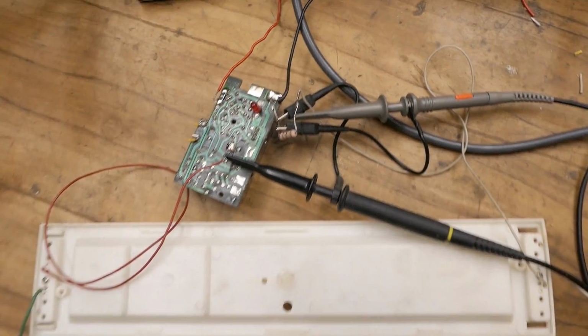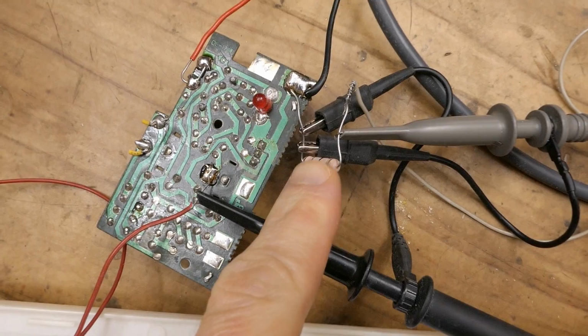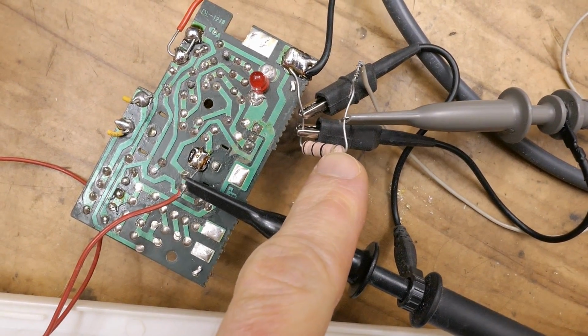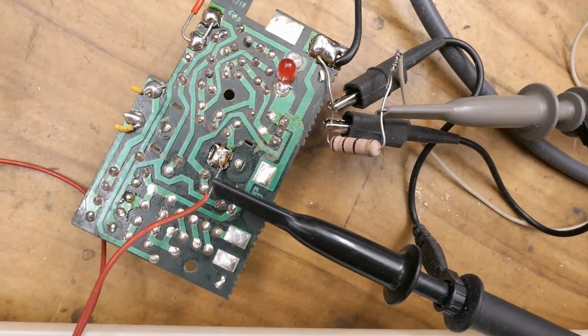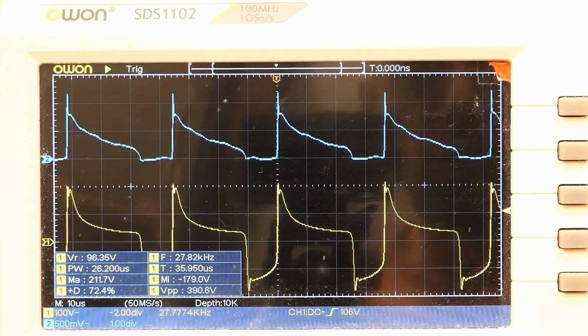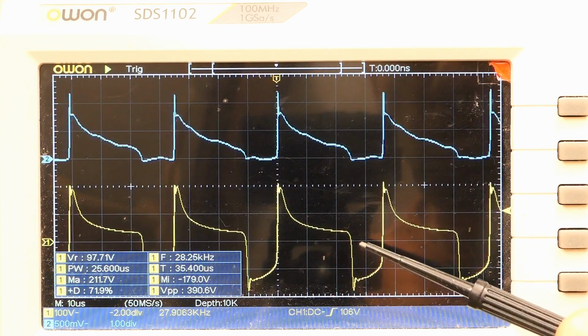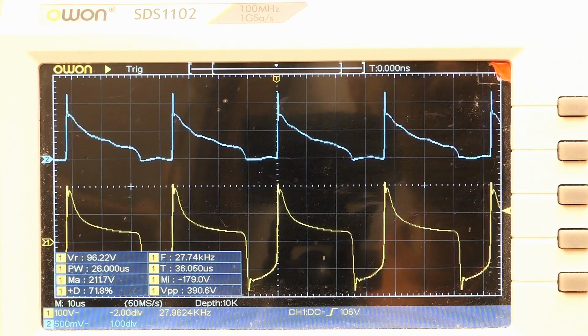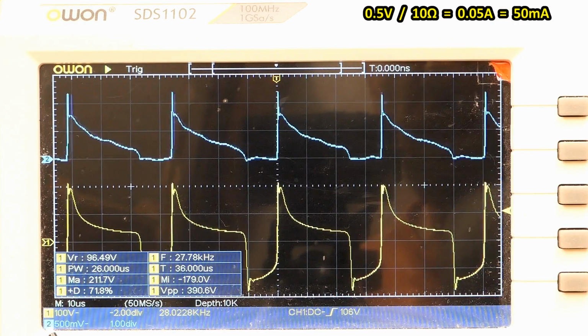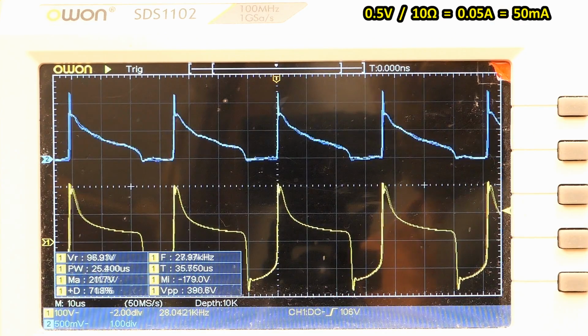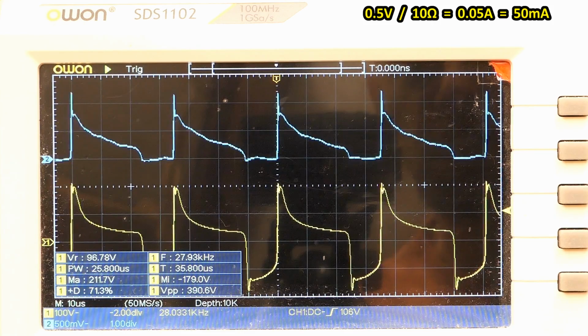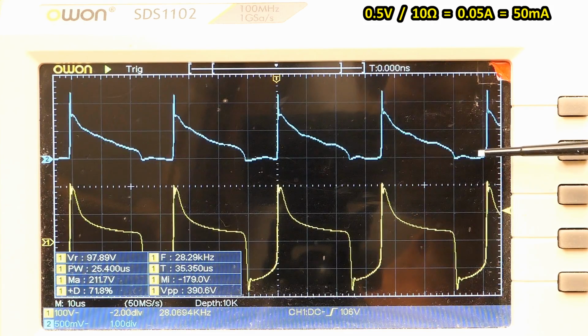I should also measure the tube current, not just the voltage. I'm using a 10 ohm sensing resistor here, and now that's the proper measurement. This is the tube voltage at 100 volts per division, and this is the tube current at 500 millivolts per division across the 10 ohm resistor, so 50 milliamps per division. The zero is here, at this level.